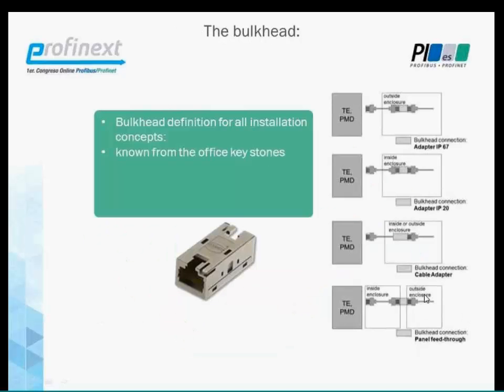We have legalized bulkheads because we have seen that there are different channel models coming from the office IT side to the industry, and why don't we use them too? So we think we can use the office typical keystones also in industrial applications. So we have legalized the use of keystones in industrial application and can build up, in addition to our typical industrial channel models, also channel models you know from the office IT.